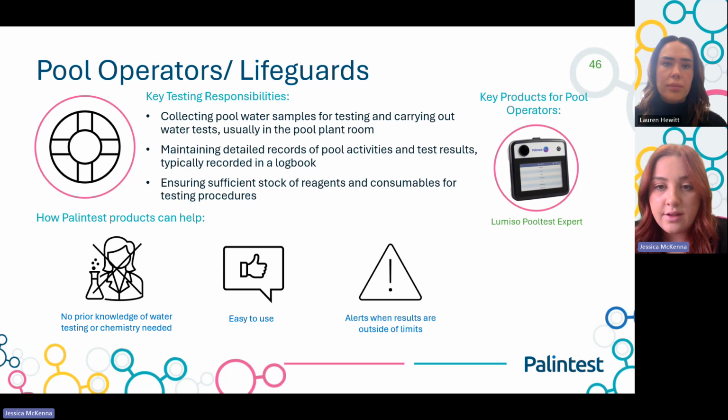test they need. The key features here are that there's no prior knowledge of water testing or chemistry needed, and the instruments are easy to use, which is important in an environment where there's sometimes high staff turnover to ensure training time is minimised. You can also set limits in this instrument based on your own regulatory guidelines, and the instrument will clearly show if the result measured is outside of these limits.